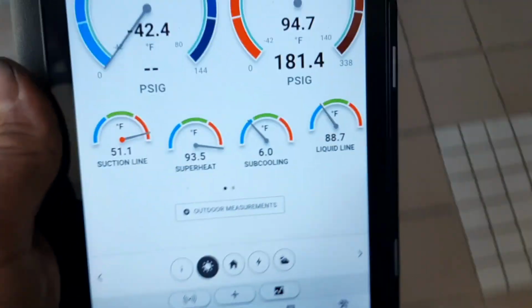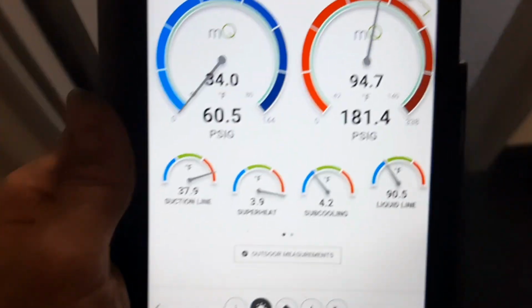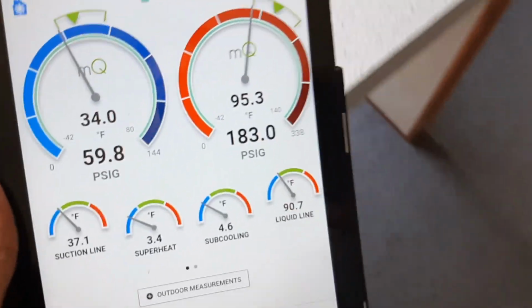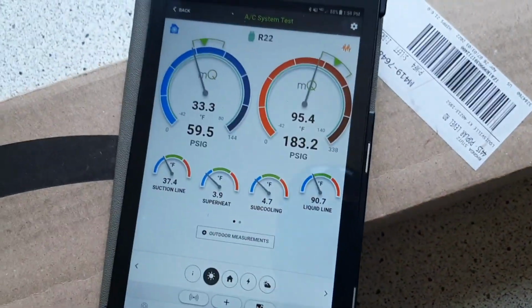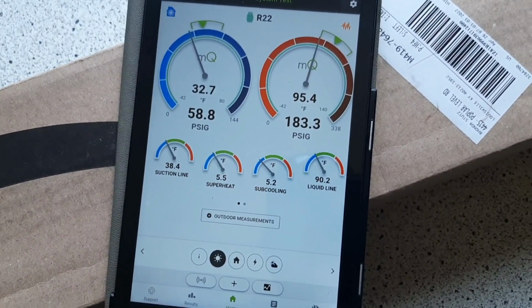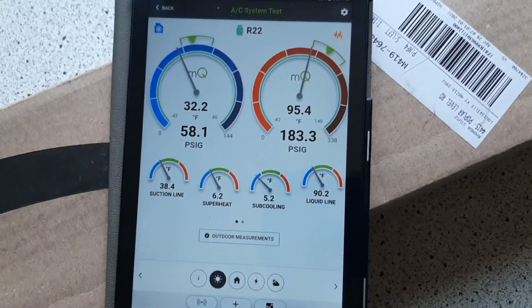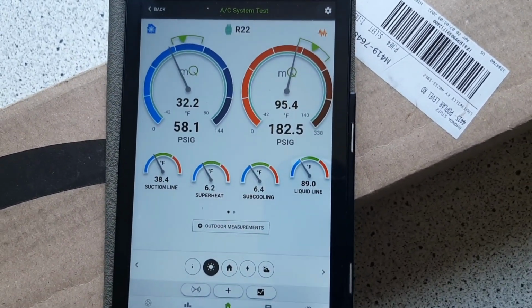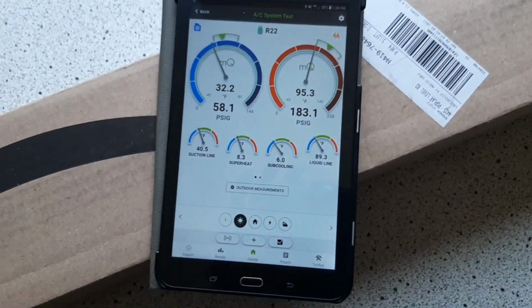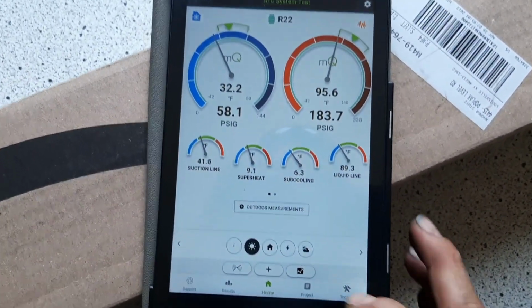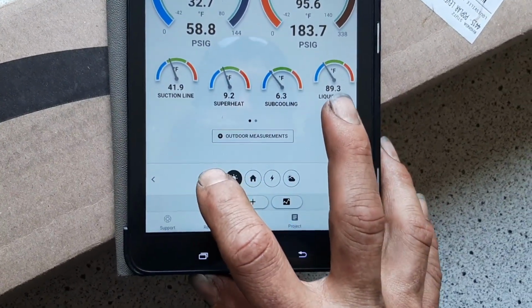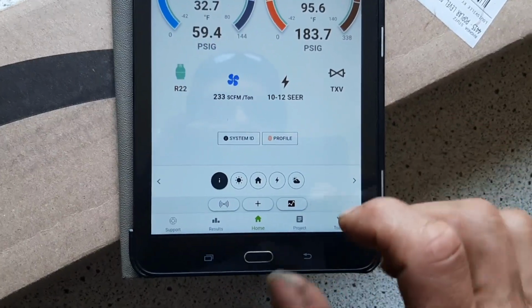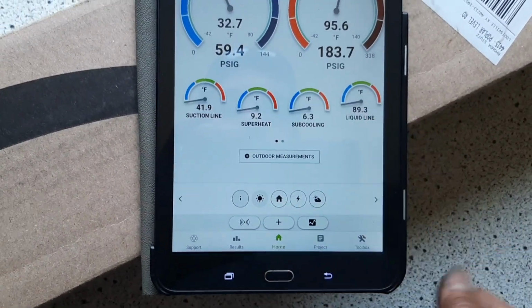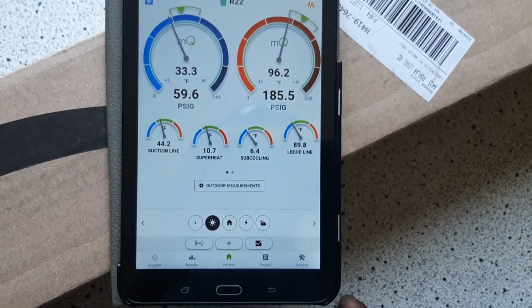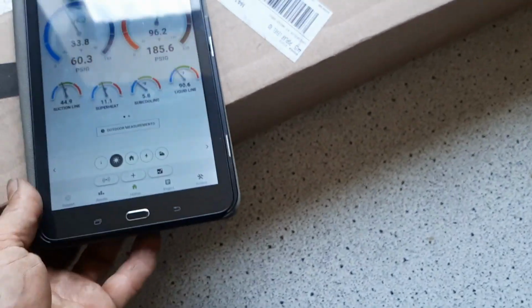Let's see if I can get my suction pressure back. But again, we're running reasonable superheat and subcooling. I mean, it's not going to be perfect. The ACs are original, so they're 1984. I set it up for being 10 SEER, and it's probably less than that. These things are old. It's a wonder they're still running. They've been running for 30-something years, and they got a new AC out there that's going to die in 5.